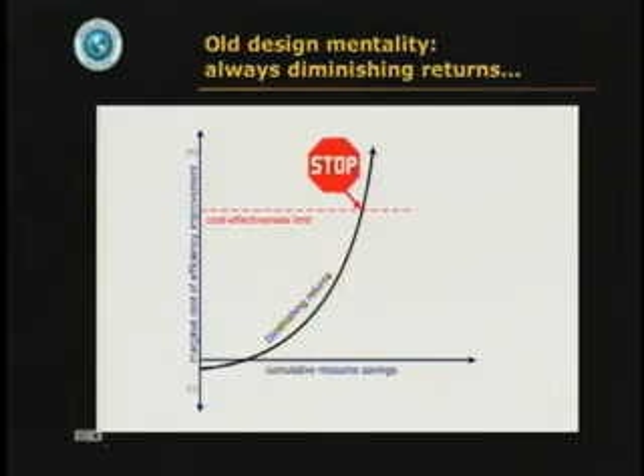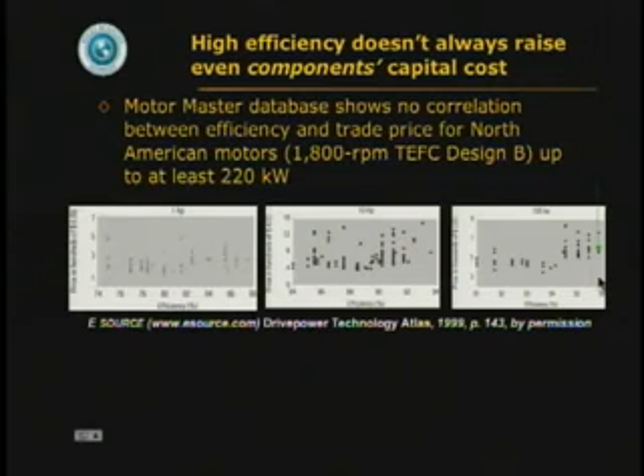But this isn't even always true at the level of components. For example, if you look at the data on motors of the most common type, up to at least 100 horsepower—actually even higher, up to at least 220 kilowatts, 300 horsepower—you find there's no correlation whatever between the trade price of the motor and its rated full load efficiency. There should be, because premium efficiency motors have more and better copper and iron, so they should cost more to make. But for whatever reason, they're not priced higher. I don't know why, but I'll take it.